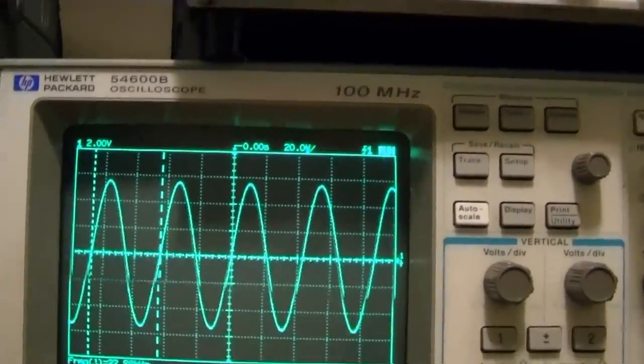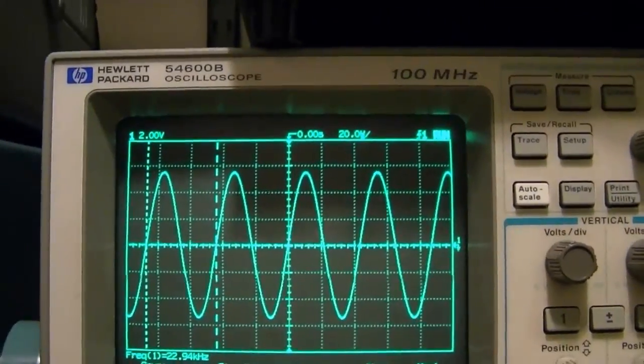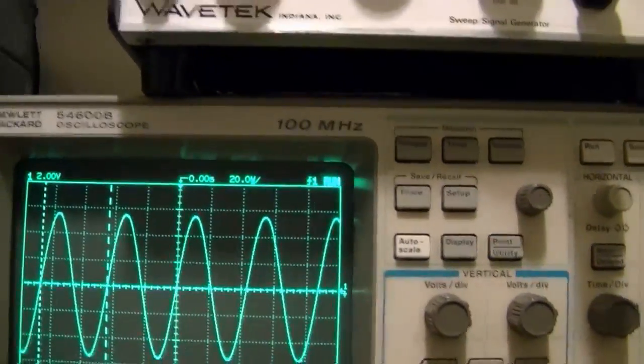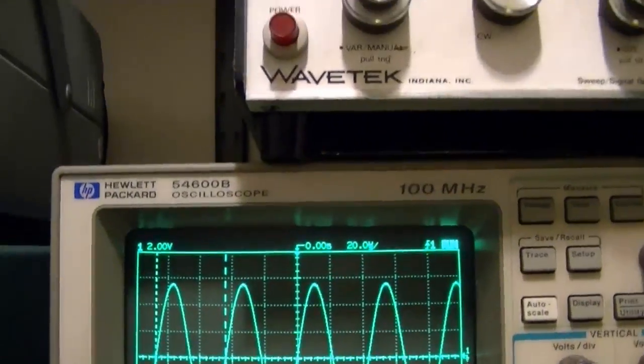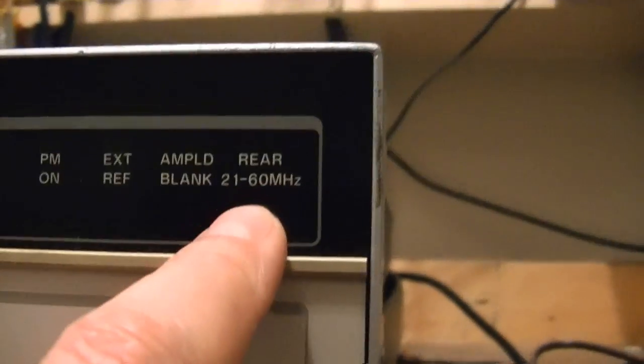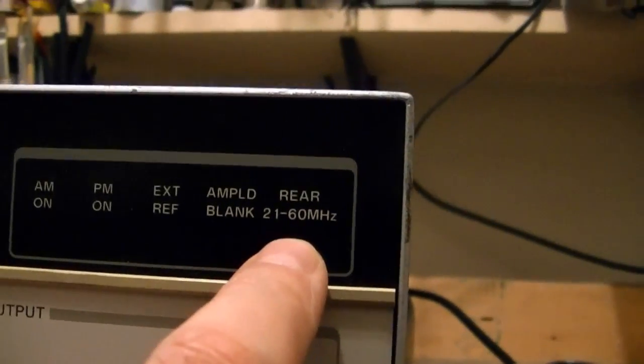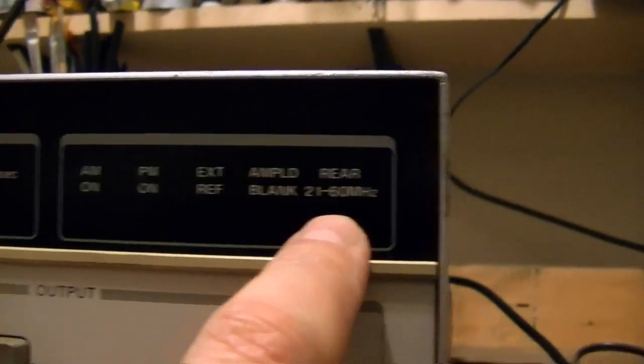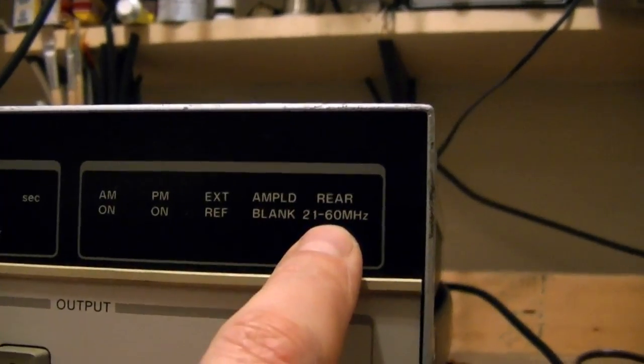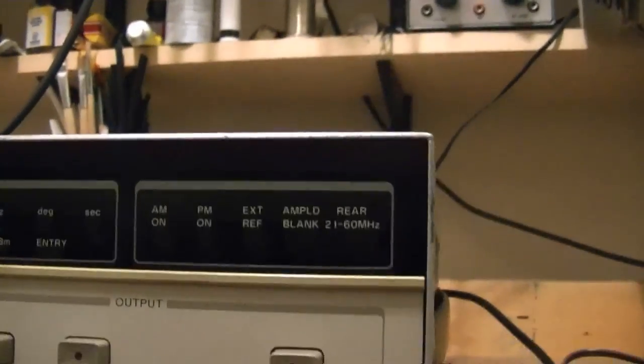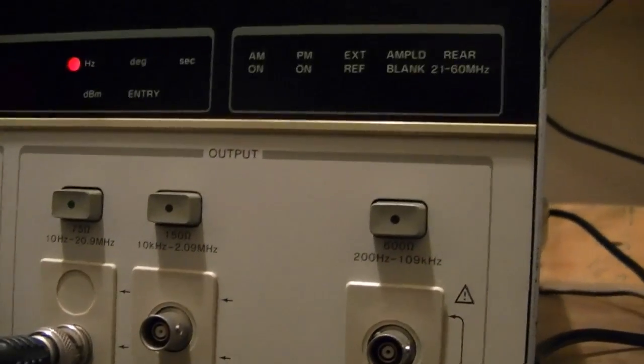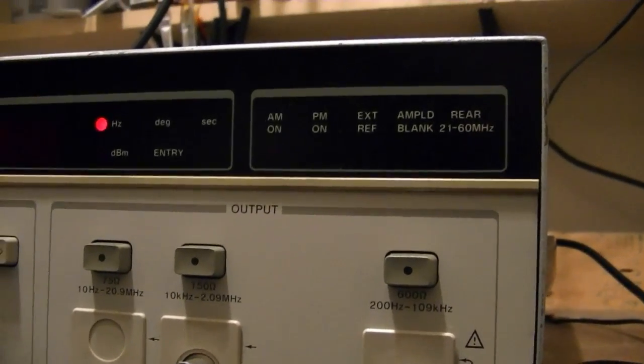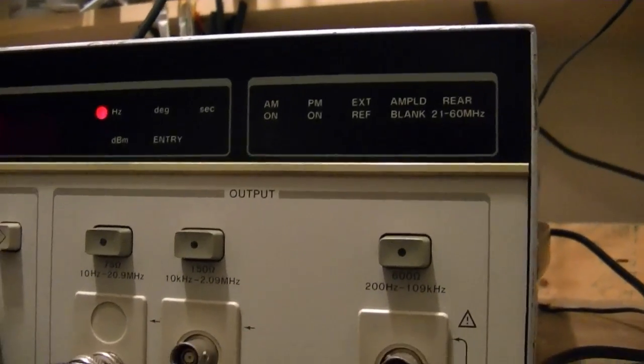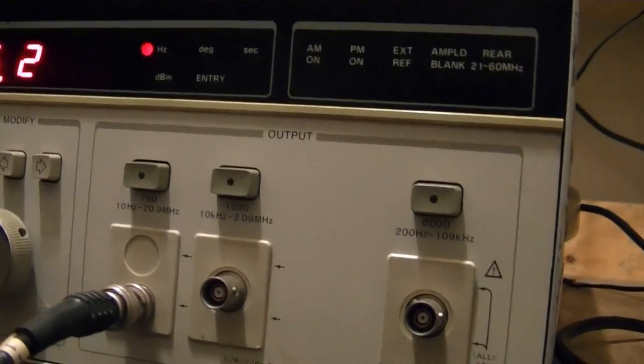Now this is something else I was curious about. It says on the front that the frequency output is 20.9, right? However, there's a signal on the back, they call it an annunciator, that if you dial in greater than 20.9, that'll flag a signal. It goes 21 to 60, so that got me thinking, why would they bother with that if this thing is limited to 20.9 megahertz? And that got me thinking, well, maybe you can go higher than 20.9. They just don't guarantee the accuracy of it.